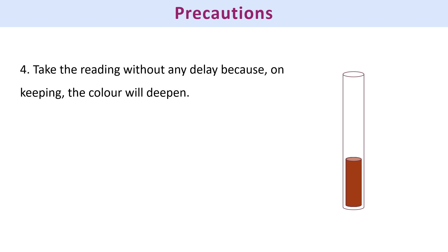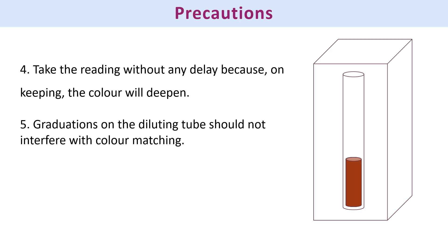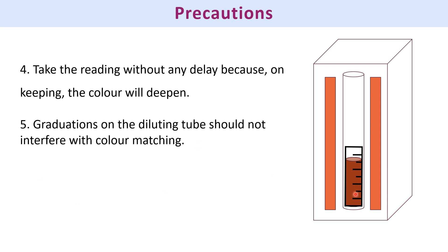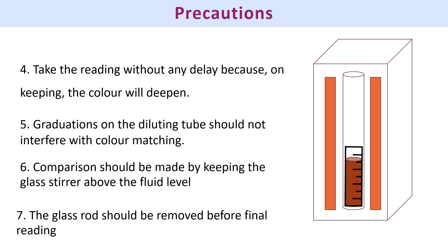When holding the tube in the comparator box, make sure the graduations are not obstructing your view, as they can make the color appear darker. The comparison should be made with the glass stirrer kept above the fluid level; otherwise it will affect the color reading. Before taking the final reading, the glass rod should be removed.